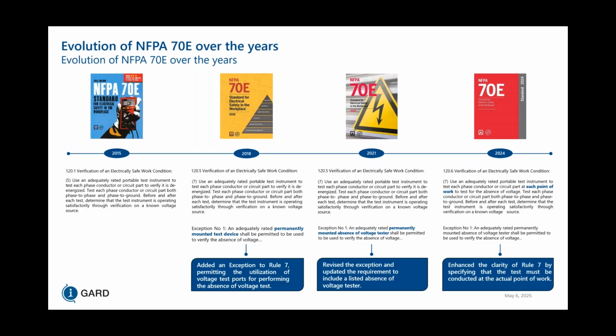In 2018, they added an exception where an adequately rated permanently mounted test device can be utilized, which would be voltage test ports. In 2021, though, they further revised the exception and updated the requirement to be an absence of voltage tester. And then in 2024, they enhanced the clarity of Rule 7 by specifying that the test must be conducted at the actual point of work. In addition to that, you can see that the numbers of the clauses have also changed over the years. We started off at 120.1, and for 2018, we got to 120.5, and now we're looking at 120.6, particularly in the latest NFPA 70E iteration.